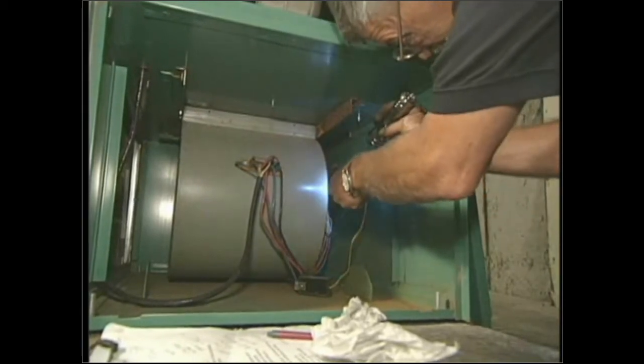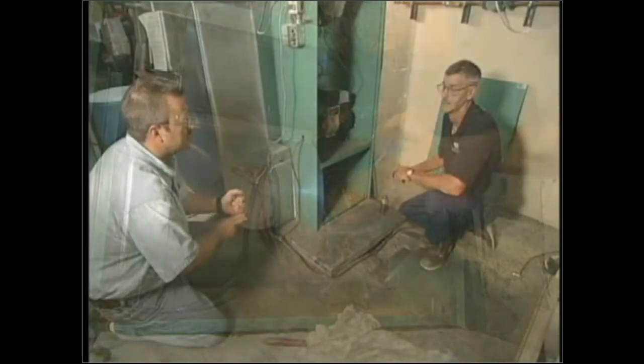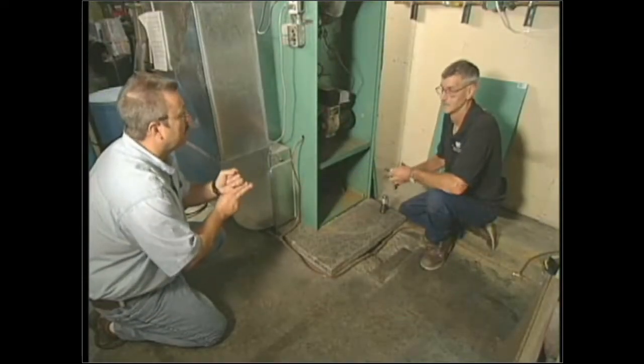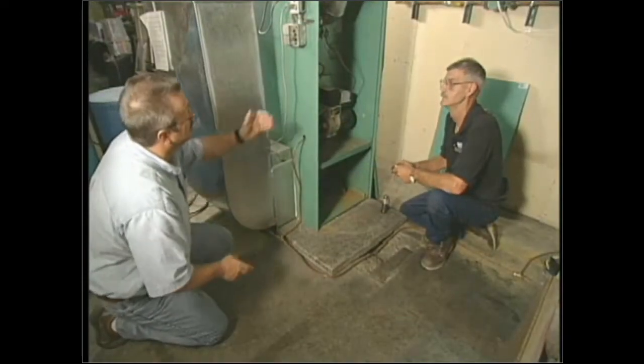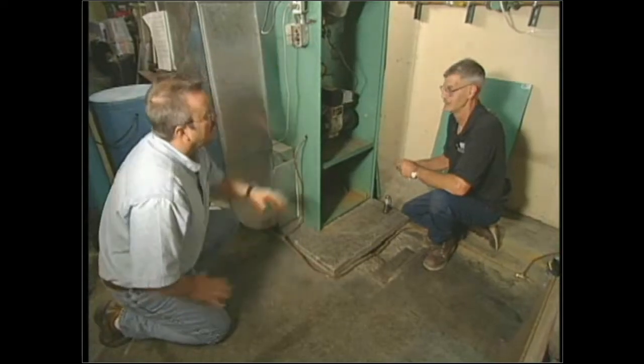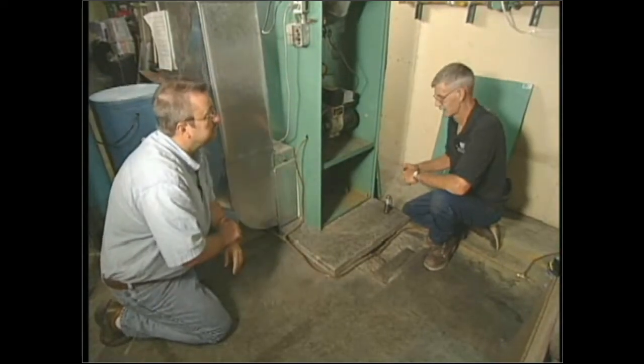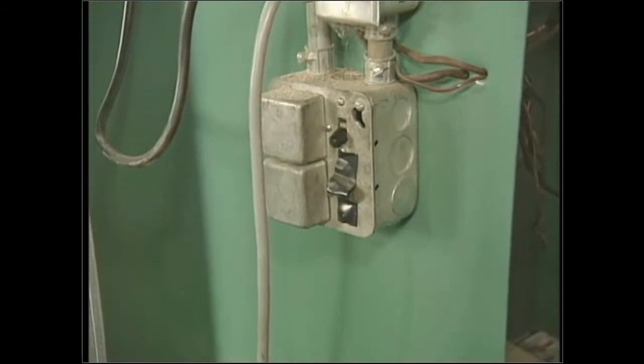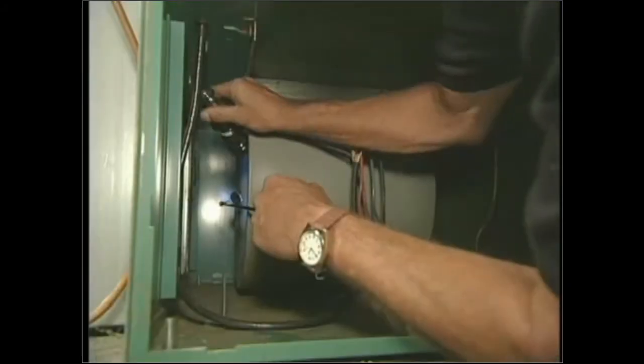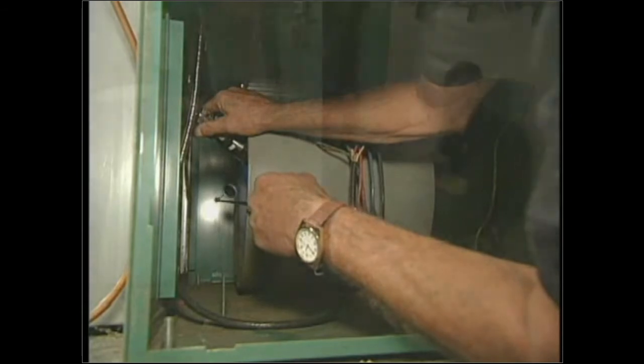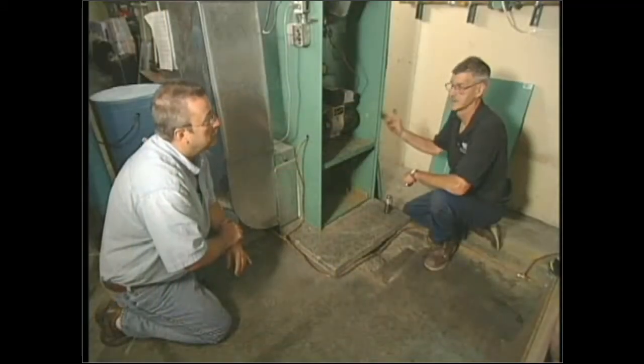Sure. So what I'm getting out of this, very important to do the visual both inside and outside before you start the diagnostic testing. And I'm assuming that you always want to have the unit shut off before you start a visual inspection. Yes, that should be one of the very first things you do, is turn the unit off, because you don't want it to fire while your hands are in anywhere else. You want to have control of that unit so you're working in a safe manner.